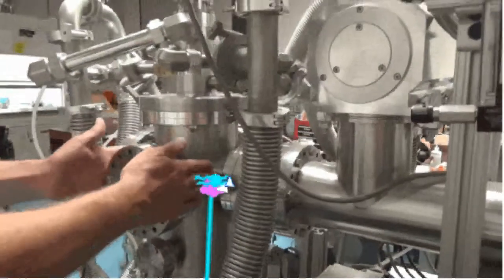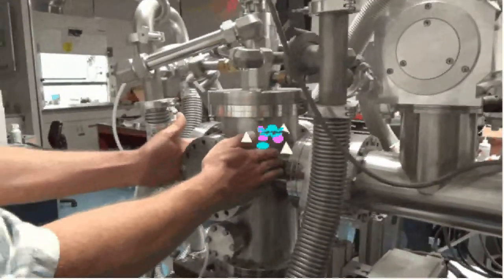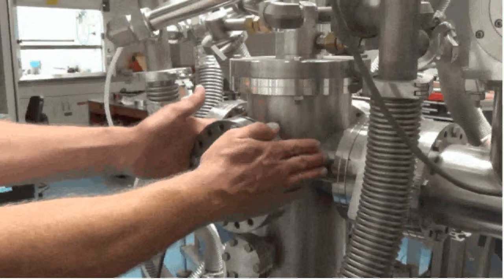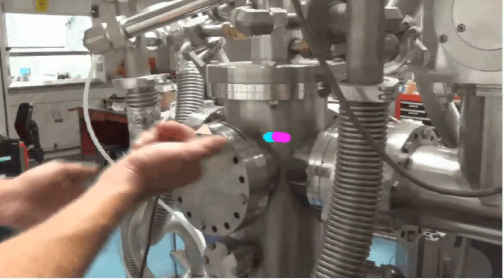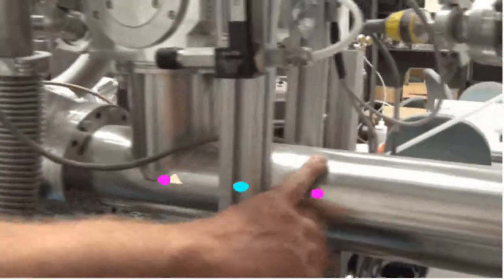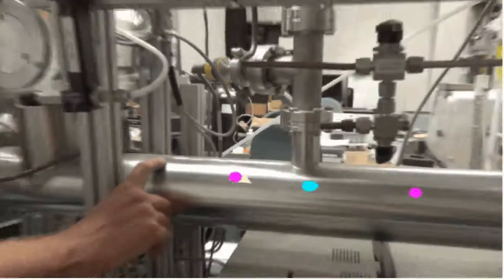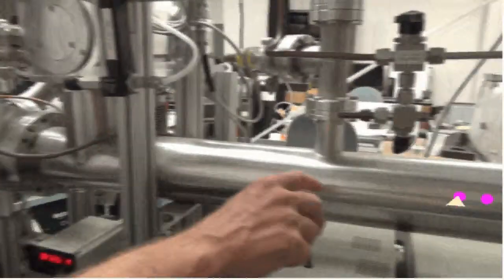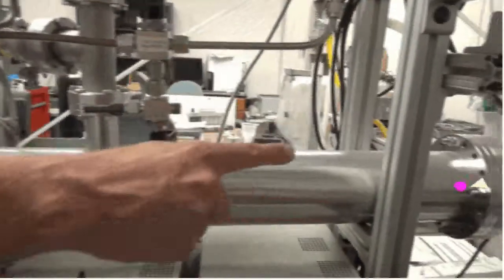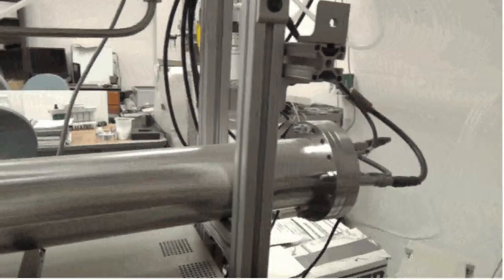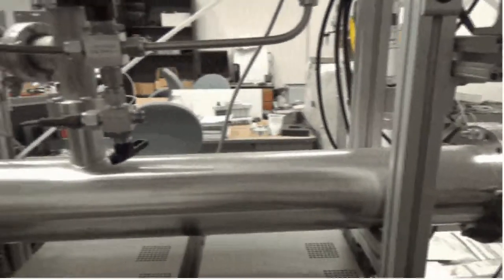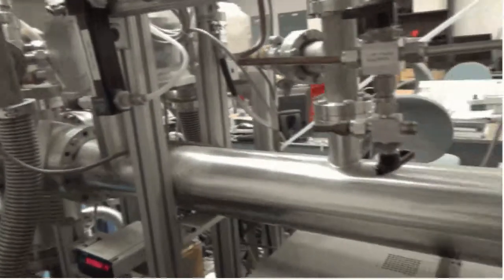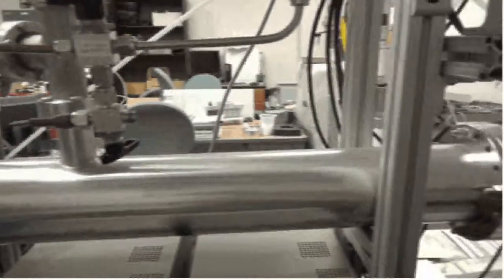It explodes into all different kinds of ions. In the source region we have 2 accelerating plates, which are held at different potentials. This potential provides the force that accelerates these ions down what's called our time of flight tube. This is our time of flight tube right here, and the amount of time it takes one of these ions to travel down the time of flight tube to our detectors at the end determines the mass of that ion. And from the mass of that ion we can determine exactly what that ion is.